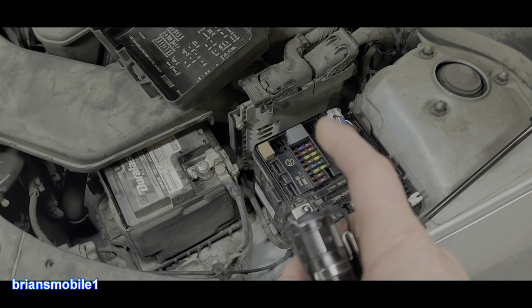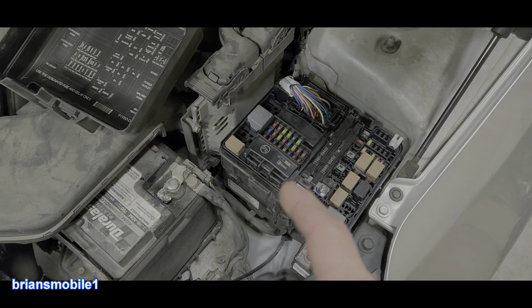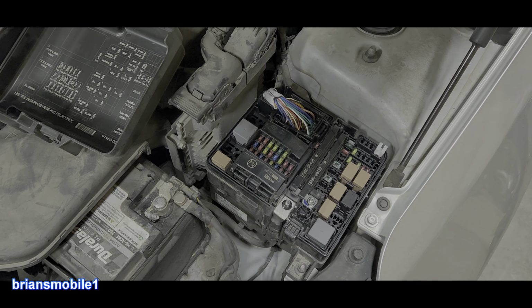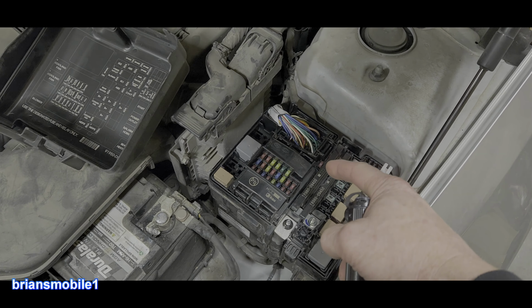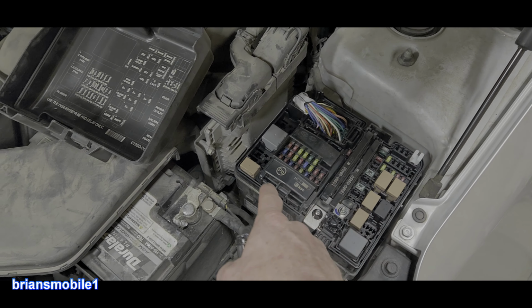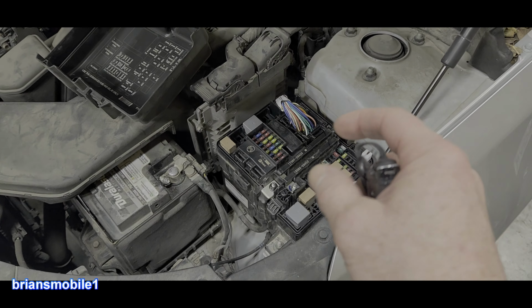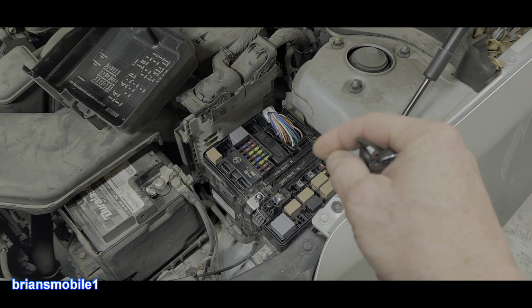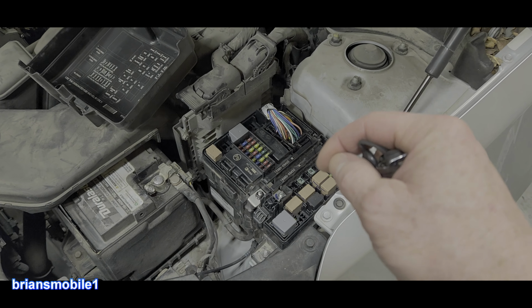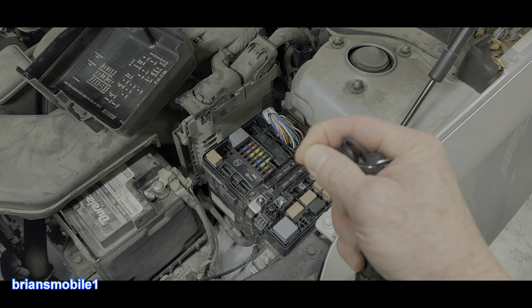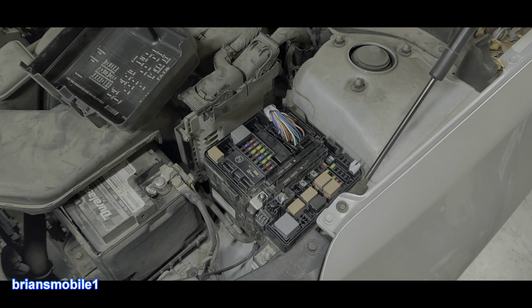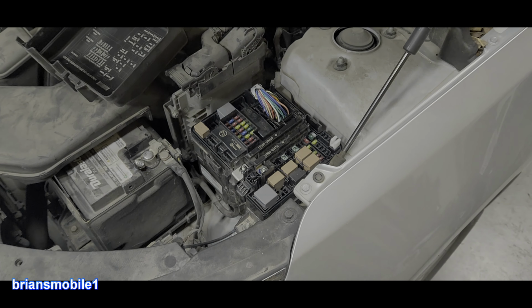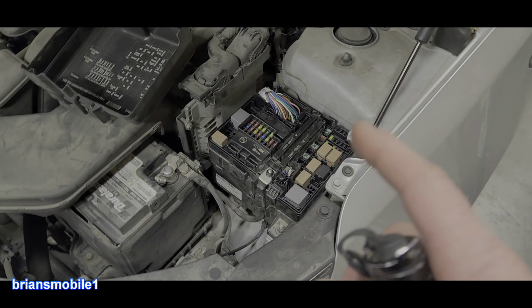If you have a drop in voltage, that means you have some resistance. The resistance was at that connection of the big fat green wire that goes up underneath there. Once I got these pulled out and cleaned up the contacts on both, then bent it a little bit so it would bite into it more, it's been fine ever since, whether it's hot or cold. I'll show you where we're at now.